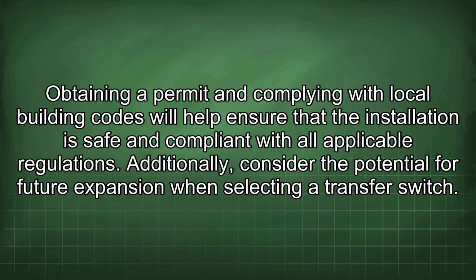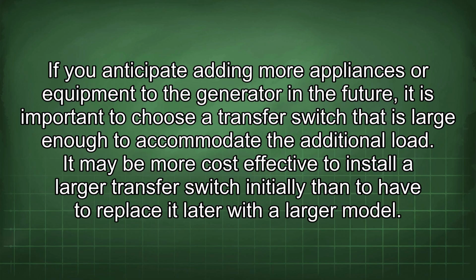Additionally, consider the potential for future expansion when selecting a transfer switch. If you anticipate adding more appliances or equipment to the generator in the future, it is important to choose a transfer switch that is large enough to accommodate the additional load. It may be more cost-effective to install a larger transfer switch initially than to have to replace it later with a larger model.